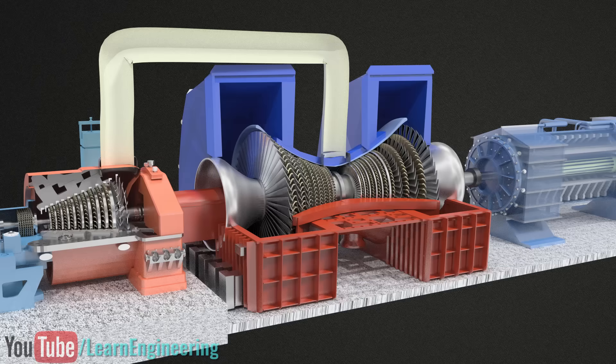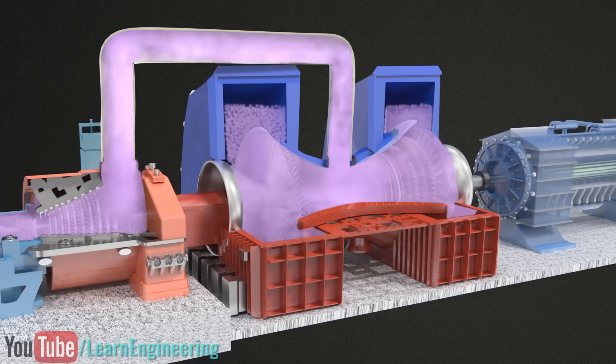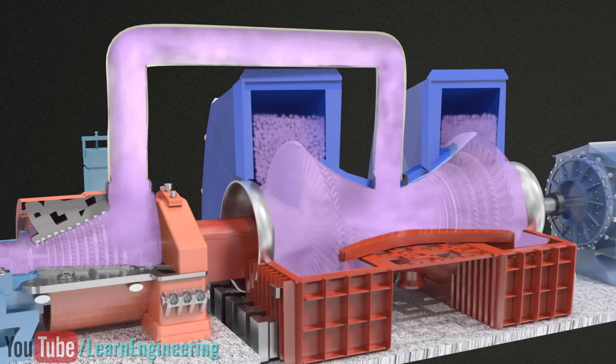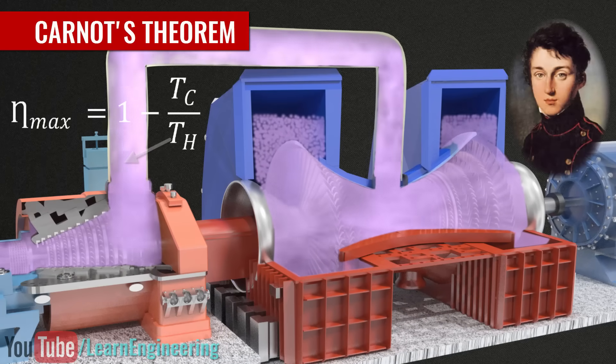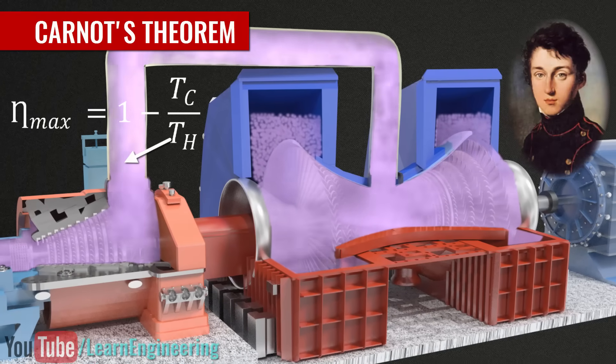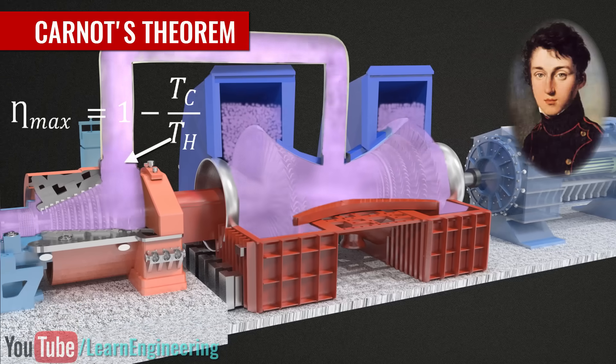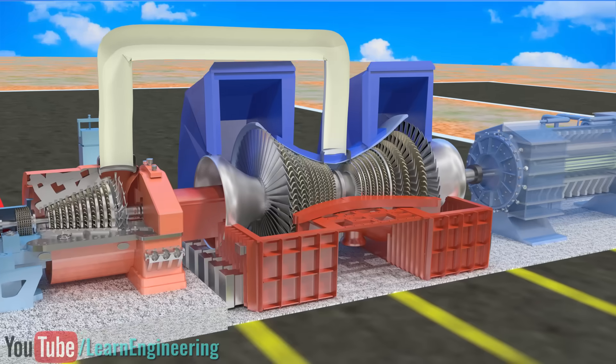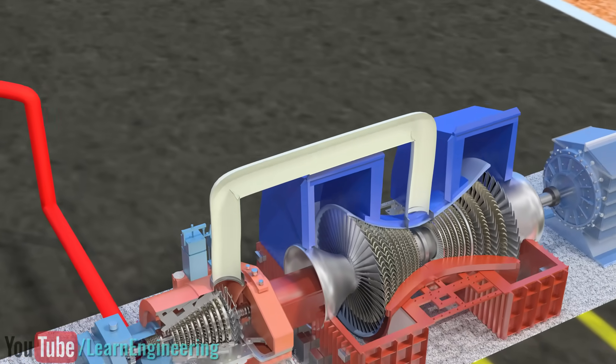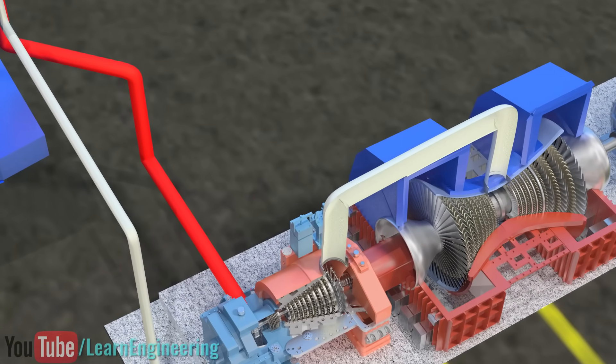The reason for such different stages is quite interesting. With greater steam temperature comes greater power plant efficiency. This is according to the second law of thermodynamics. But we cannot have temperature greater than 600 degrees Celsius, since the turbine blade material will not withstand temperature more than that.